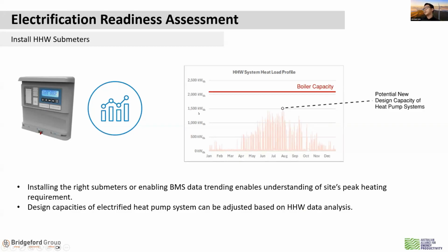And so rather than installing, for example, a 1.5 megawatt system, if you can be certain that these spikes do not come in subsequent hours, that there's definitely going to be a gap before the next spike, you can size it down to, for example, 1.25 megawatts, and install 10 kiloliters of buffer storage on the site to help smooth out the load. So your heat pump doesn't have to be the one supplying the heating for the additional 250, your buffer storage is just doing the work.